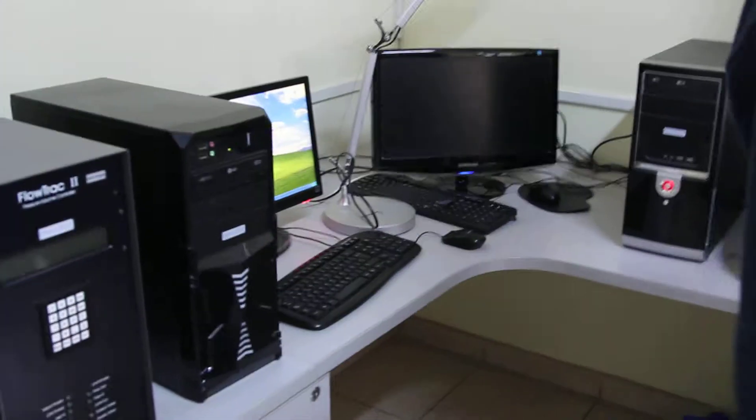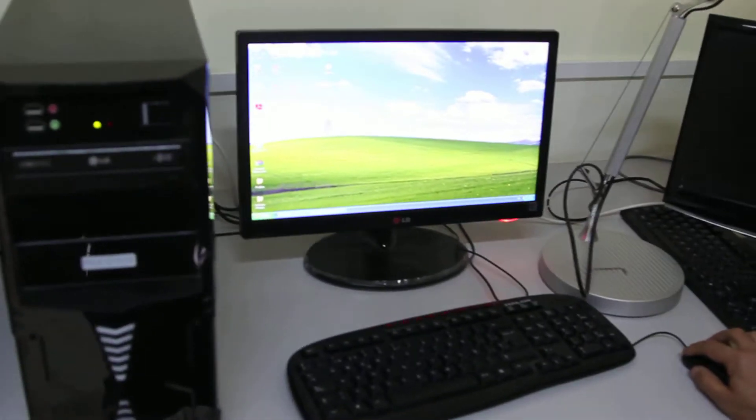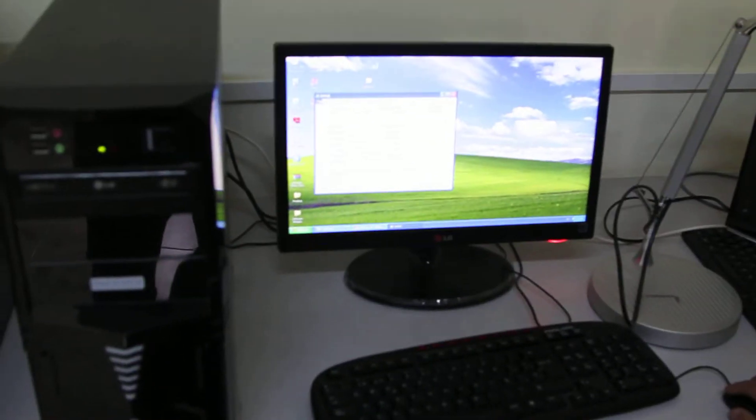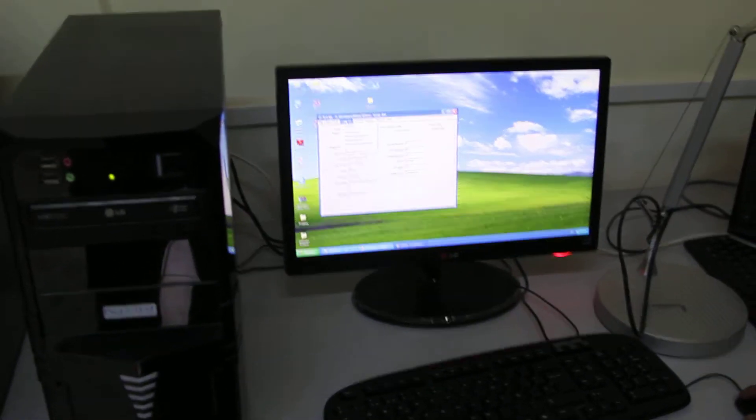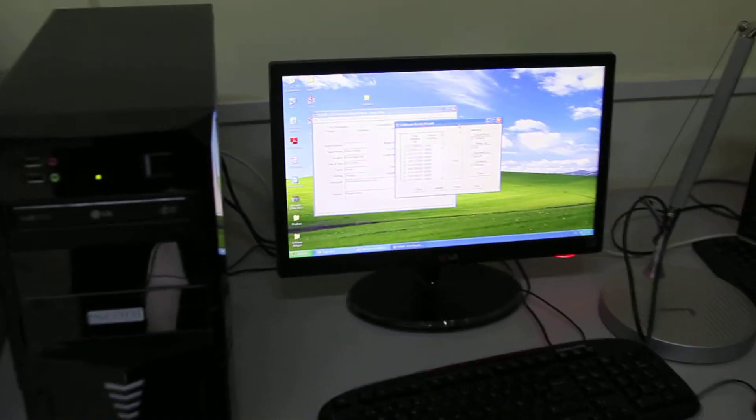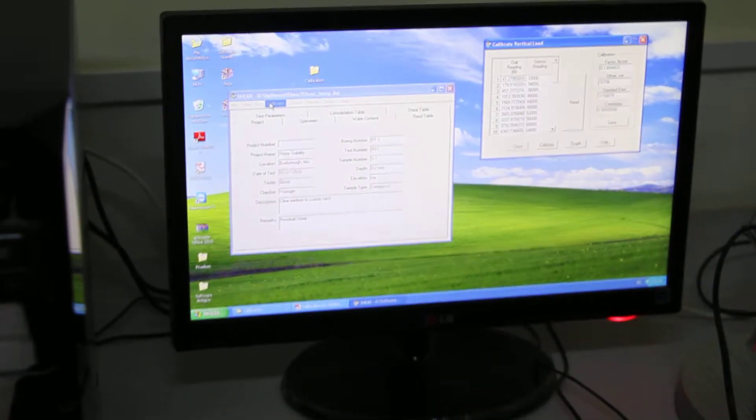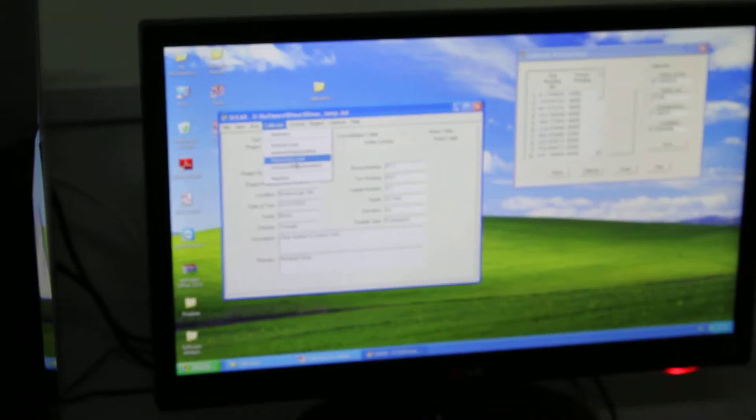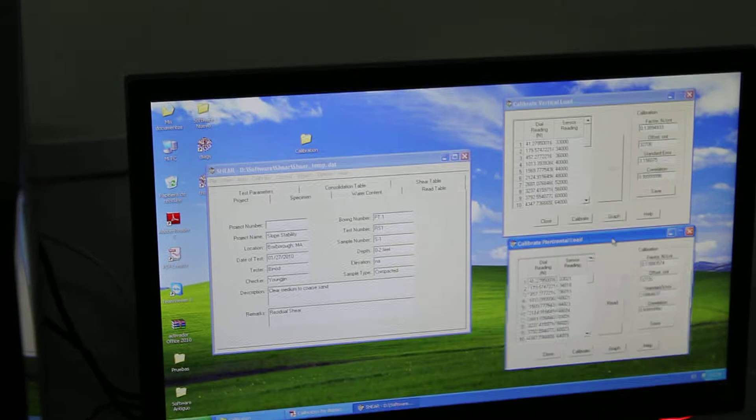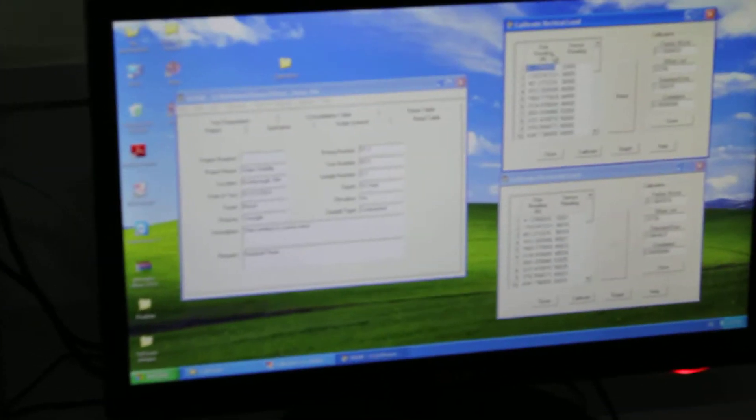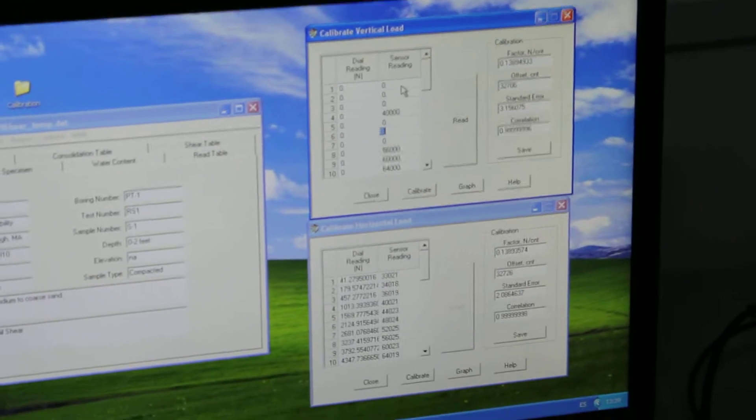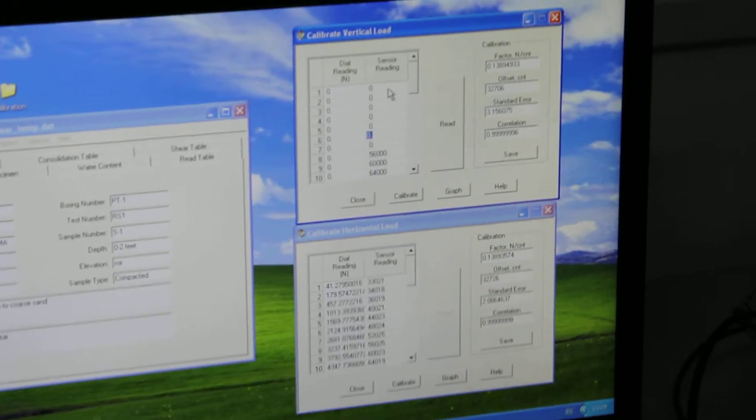I'm going to open the shear software and in the shear software I'm going to open a file. I'm going to calibrate vertical load, I will open the vertical load, calibrate horizontal load. And what I'm going to do is I'm going to zero everything here and there so I'm going to re-zero everything. And so I'm starting from scratch.